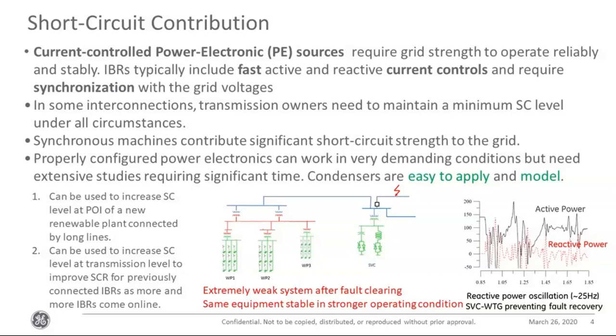Right, and there's an example down here where we had three wind plants connected near an SVC that was connected by a very long line. And when a fault was applied, it prevented recovery post-fault because we saw these very high frequency oscillations between the SVC and the wind.